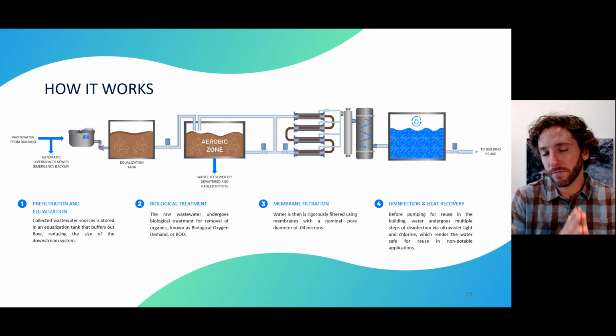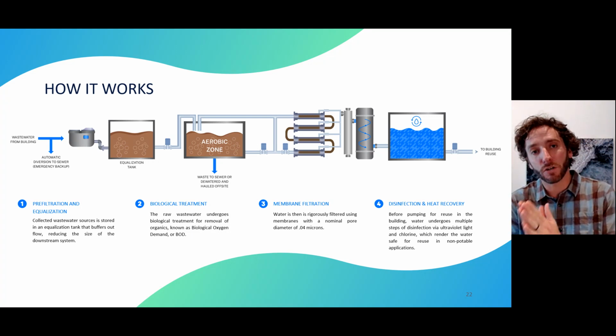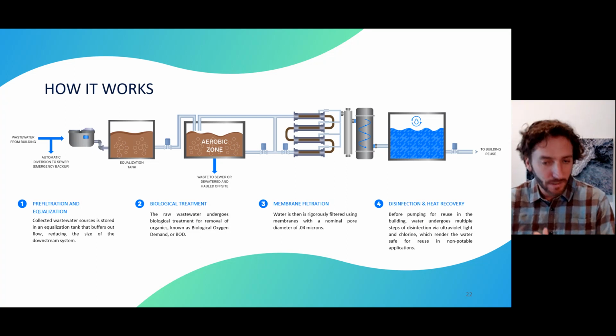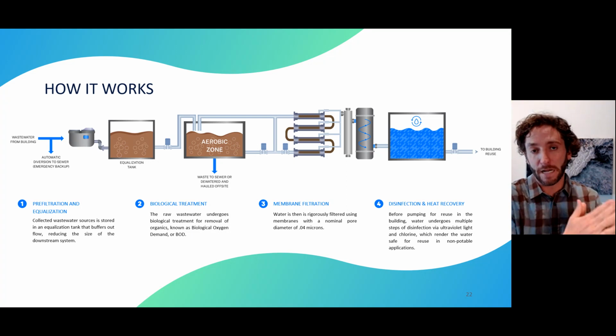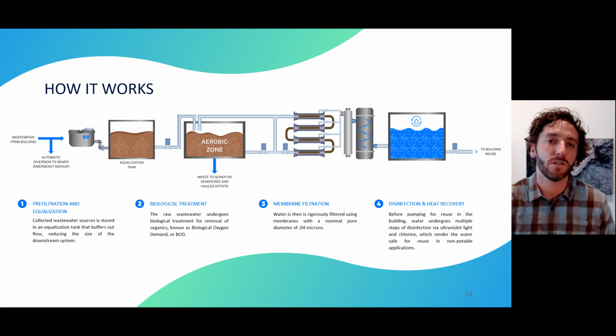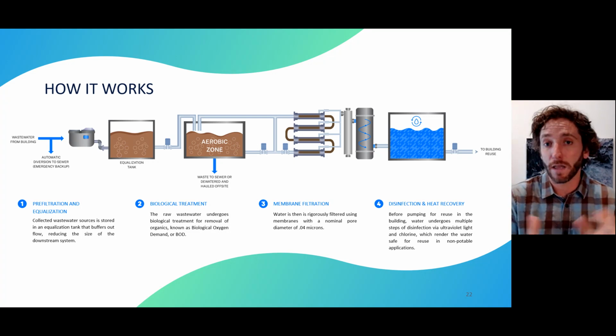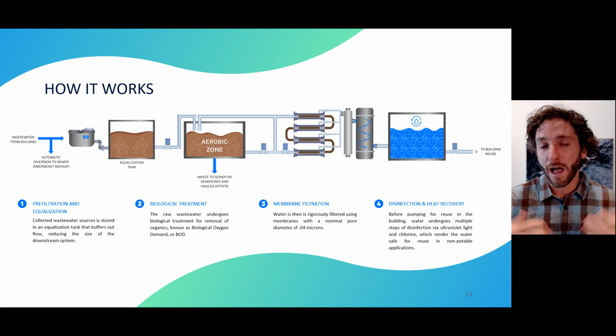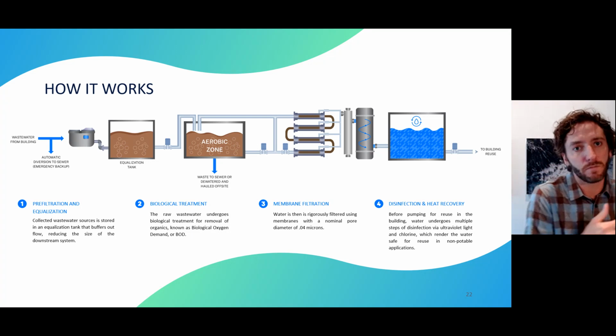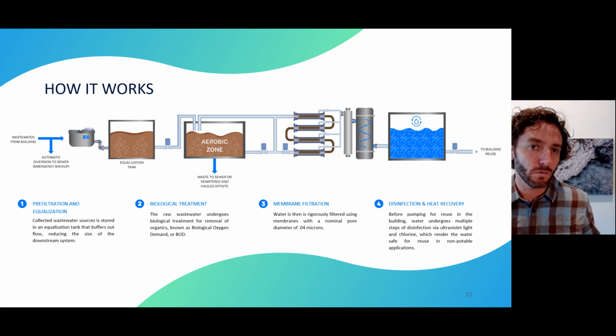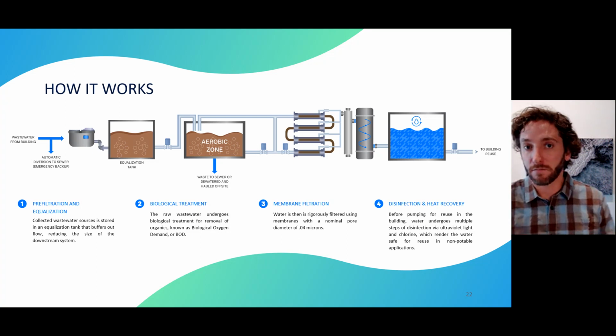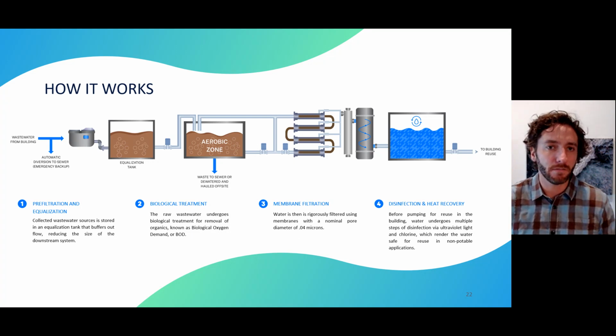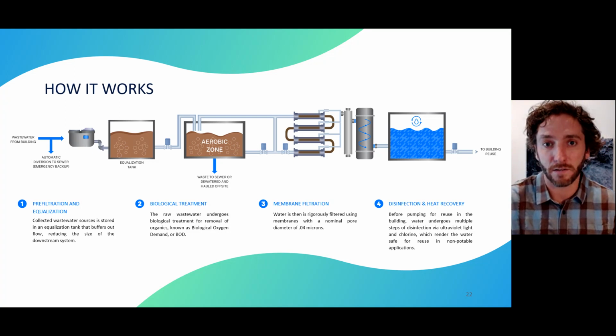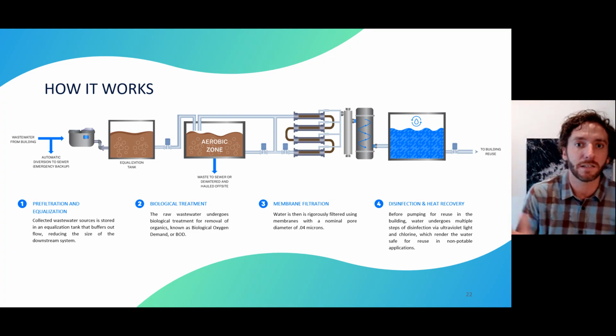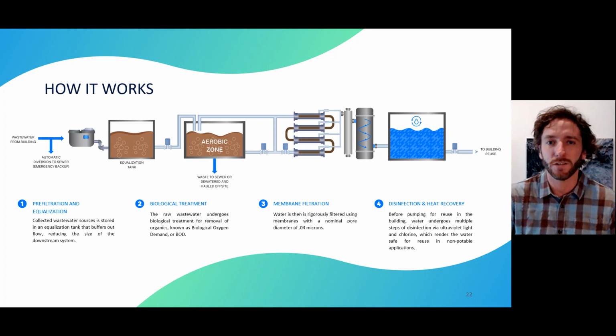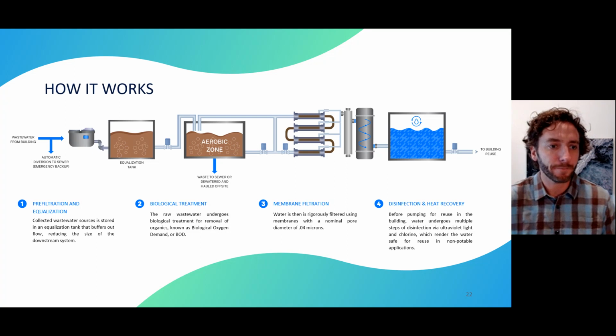We install a three-way valve that is basically spring return closed. So in the event of a power outage, that valve by default spring returns to send everything to the sewer. This is a great reliability feature to make sure nothing out of the ordinary happens in terms of backing up the basement of your building. Of course, you'll also have sumps and drains in the basement as a duplicate measure, but those will be there as a contingency, hopefully never really used outside of collecting foundation drainage or little drip leaks as they may occur.